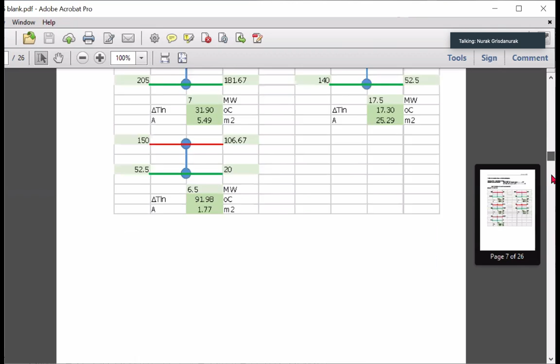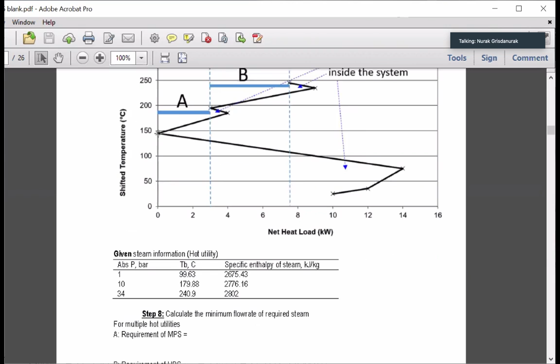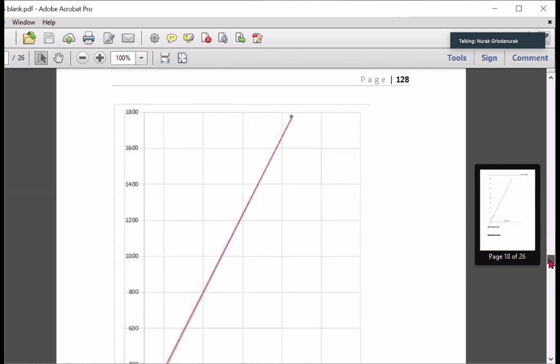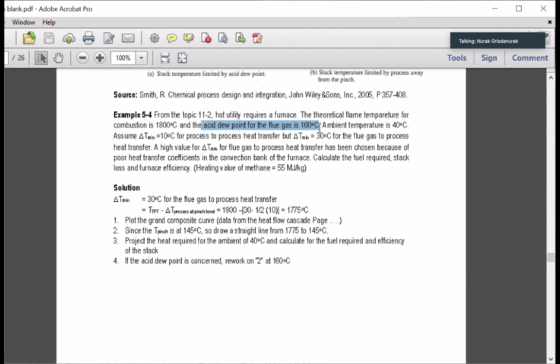So the graph is compressed, the dots are really close together but not at the same point - this is going up to the maximum, 240, 250 degrees Celsius. I meant 160 and 145 - 145 is for our pinch point. But in this case, our fuel contains some sulfur, so I need to be concerned about the acid dew point, which is 160 degrees Celsius, so I have to draw that one.